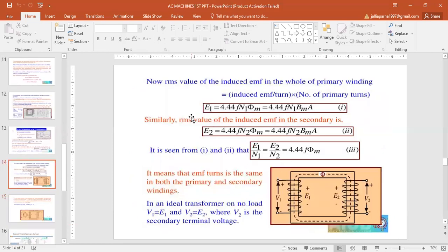Now the RMS value of the induced EMF in the whole of the primary winding equals the induced EMF per turn into the number of primary turns. So E1 on the primary side equals 4.44 into f into N1 into phi max, which is 4.44 f N1 B max into area. This is the first equation.